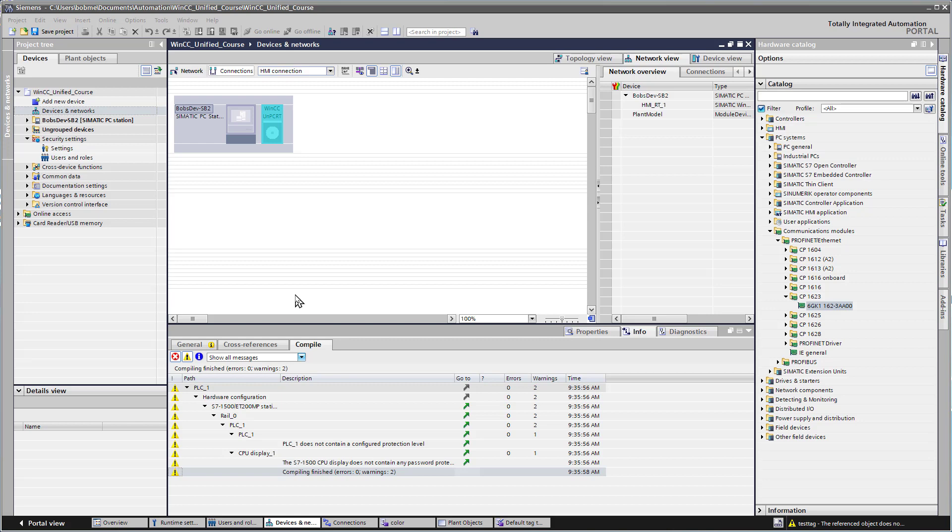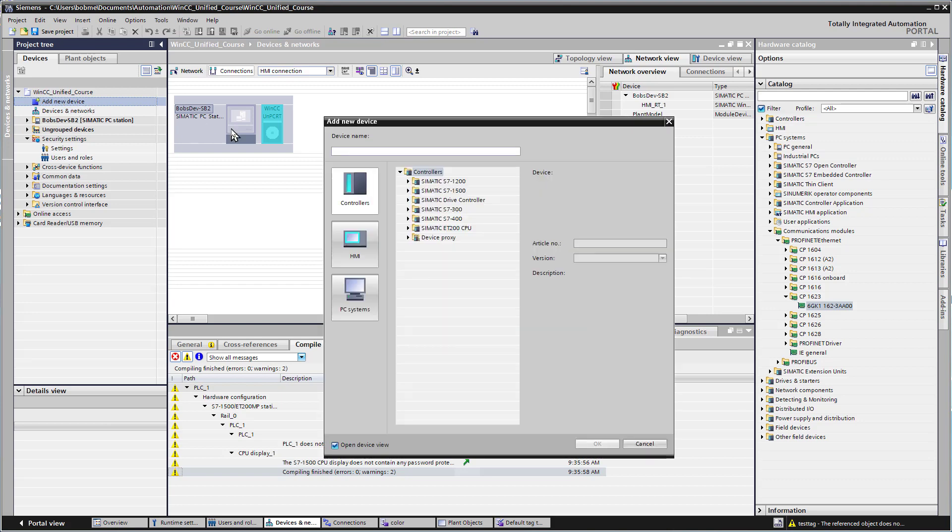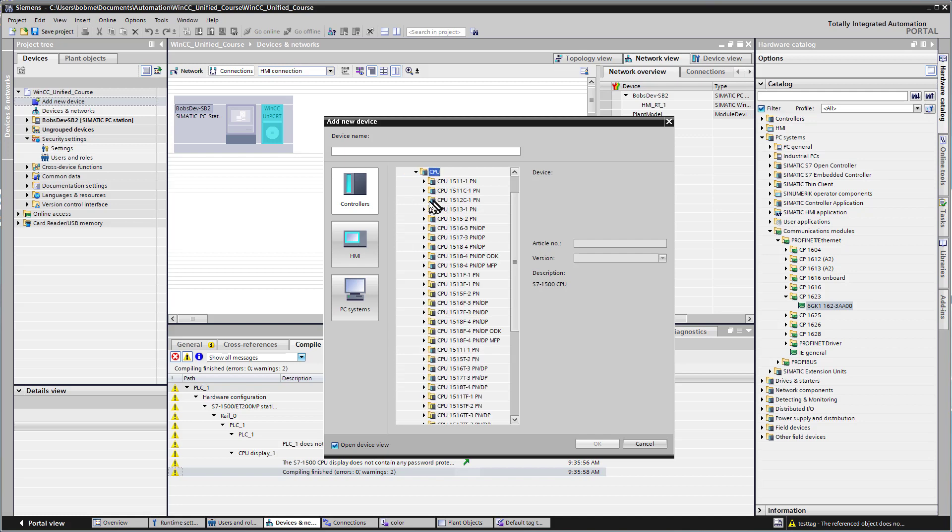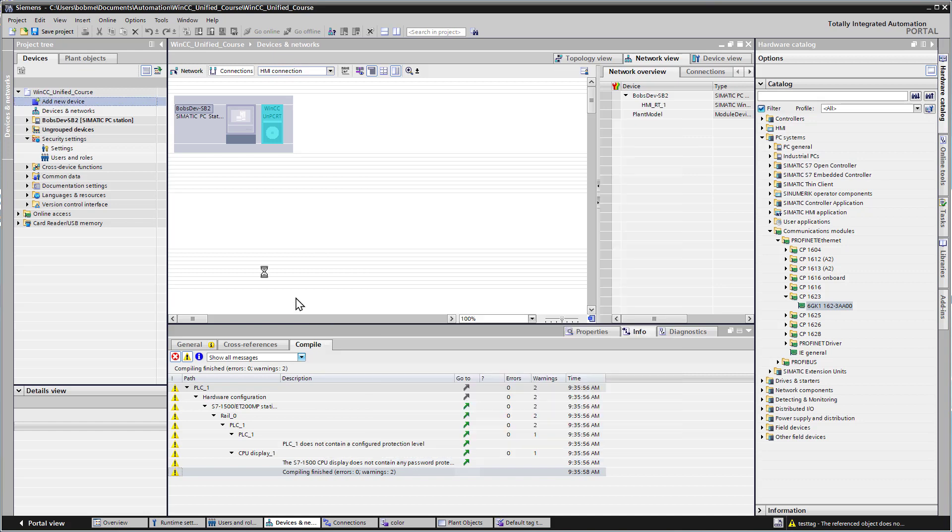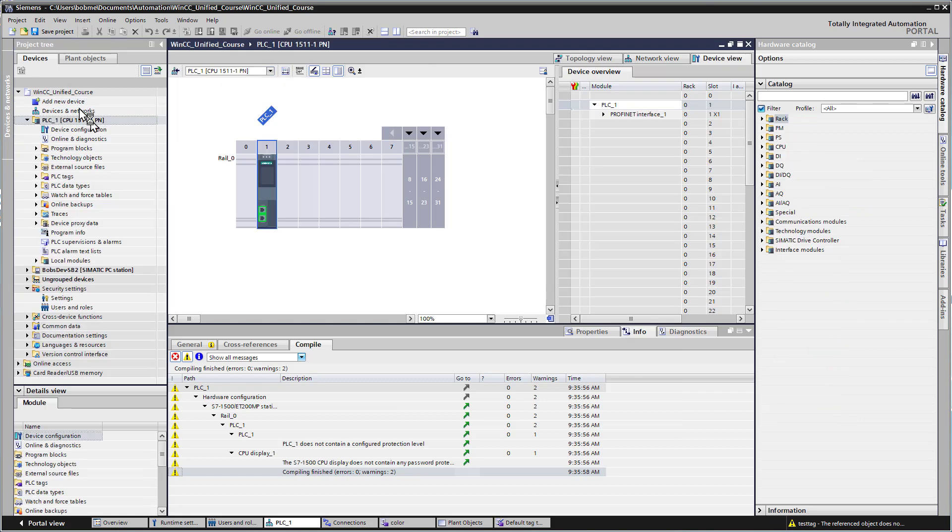The first thing we need to do here is add a controller device to our project. I'm going to go to Add New Device, Controllers, and then under S7-1500 CPU, I'll add a 1511PN, just the first one. I'll click OK, and it's going to add it into the project.